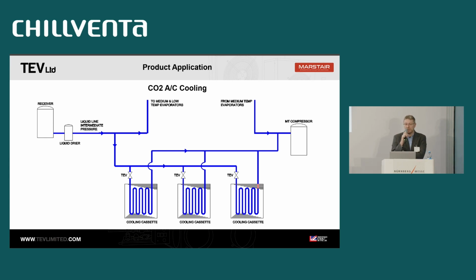The receiver, normally on the intermediate pressure, is around about 0 on CO2 systems, and that's about right for air conditioning. You don't want to be evaporating too low for any kind of air conditioning system. If you evaporate way too low, what happens is that you do a lot of latent duty instead of sensible duty. What I mean by that is you're creating a lot of condensate and drying the air out, but not doing a lot of actual temperature cooling. So you want to try and keep the evaporating temperature of the system going into the cassettes for cooling around about 0 if you can. That way you're getting the best in terms of sensible cooling and not just drying the air out and becoming some sort of dehumidifier. Okay.